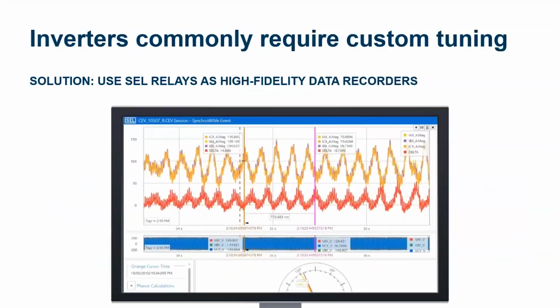Inverters require a lot of retuning. And this means you need a lot of data collection to know, did that tuning help or hurt the situation? In this case, you see SEL relays being used as high fidelity data recorders, not only with fast sampling from event records from the relay, then extracted to be viewed by SYNCHROWAVE Event, but also regular streaming C37.118 data held to a historian we call SYNCHROWAVE Operation. I can't even imagine commissioning a microgrid job without SEL relays and SYNCHROWAVE Operation. In fact, I don't. And please don't you either.